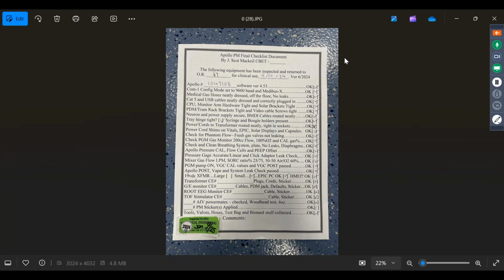So then the next thing I check is the gas analyzer. I'll run the calibrations. Can this thing go in service mode? Oh no, it's locked. Some Apollos, the service mode is locked out, and you have to use a service software to open the service mode. If you do a software upgrade, that's the time and the only time you can check a box to not require use of the service laptop. So we only figured that out halfway between doing the 4.53 software upgrade on 60-something machines.